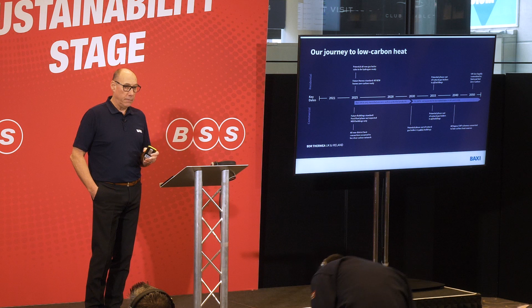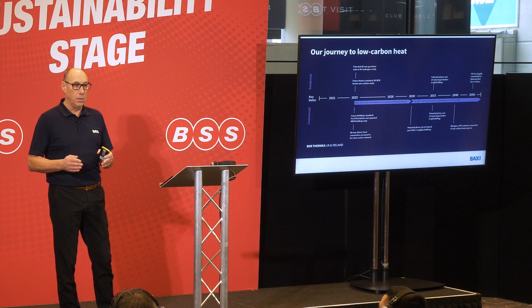Around about 2040, there's a review of CHPs, because at the present time a large majority of heat network systems will have a CHP attached to them, and they're looking at the validity of CHPs. Well, CHPs can be quite easily adapted to run on several fuels. So as we reduce the carbon emissions of the fuels we use today, the CHPs will carry on running. So in 2040, 2050, we may still see a lot of CHPs on the system. To give you an idea, at the moment there's about 3,700 sites in the UK that have CHP units. The grid network can't afford to take those offline, because the grid would collapse. So there's a major benefit in keeping CHPs online.